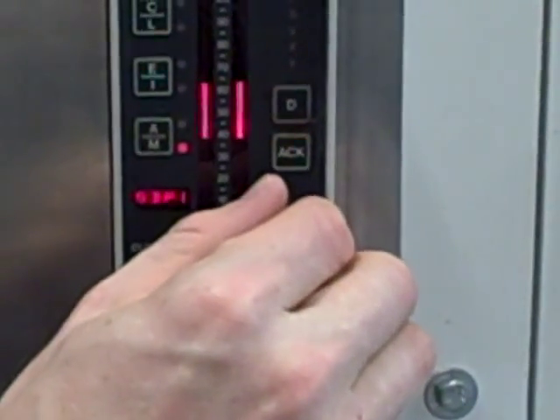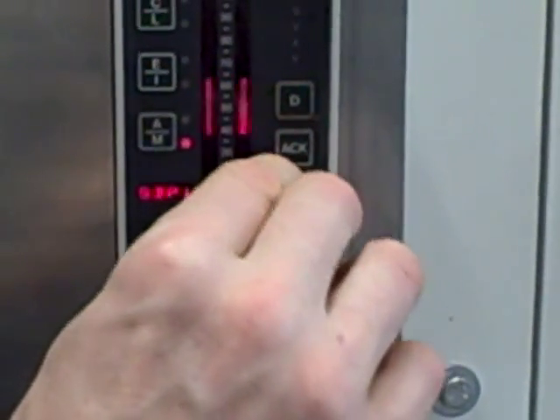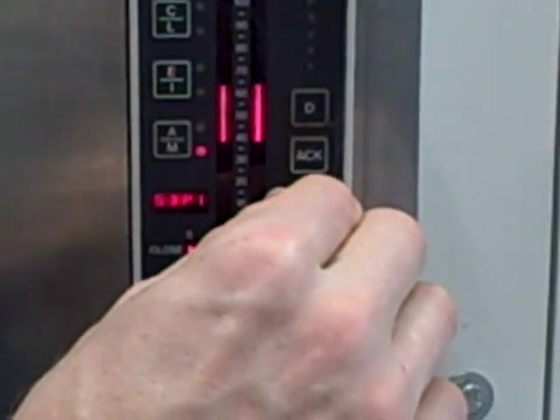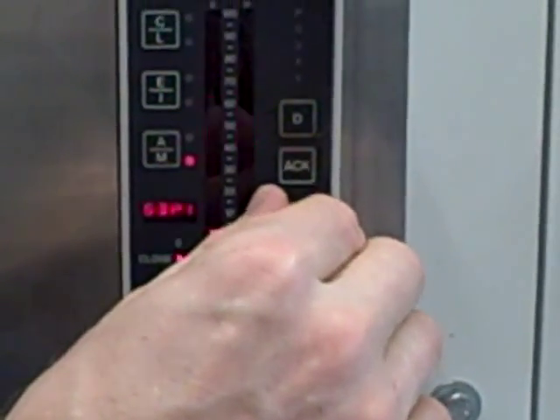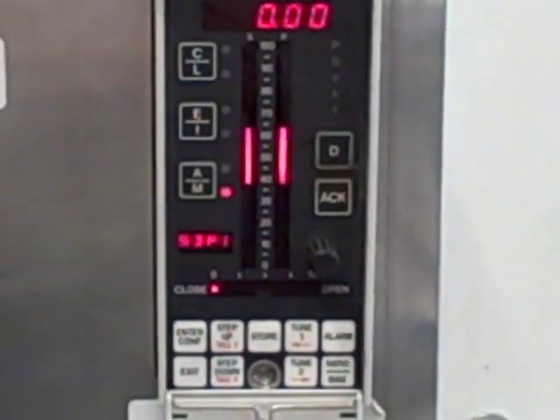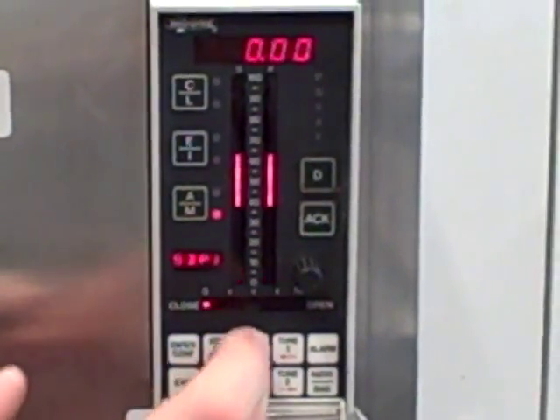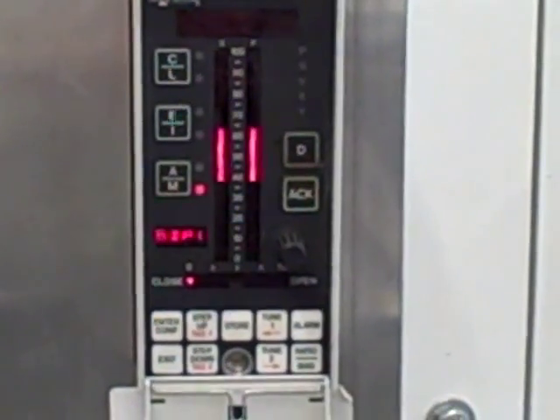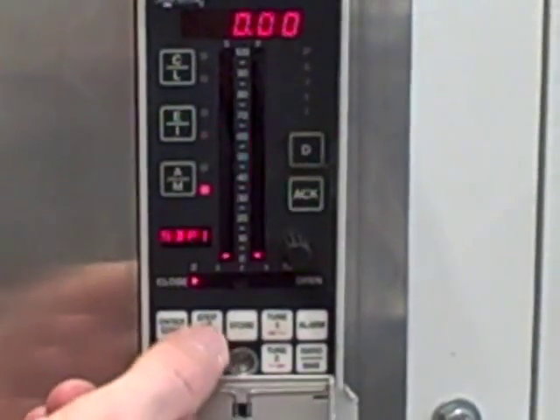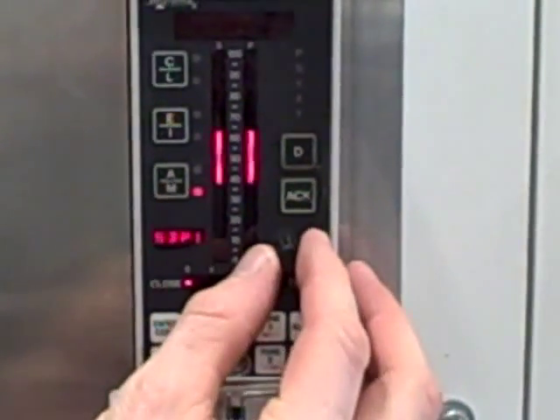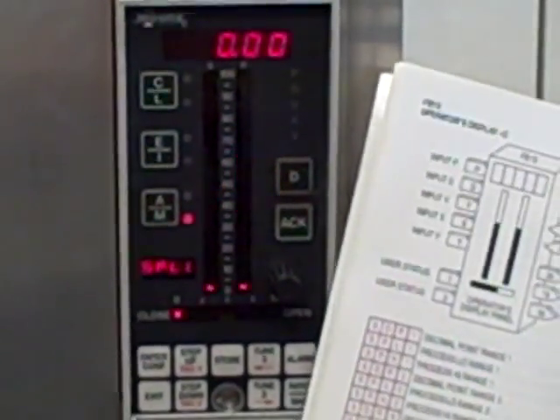That's how I set the number of decimal points I have there. So I shouldn't say number of decimal points, the number of digits past the decimal point. I'm happy with what I have, so I hit store. I will now step up into the menu structure and move one over to my next parameter, SPL1. SPL1 is process low range value 1. Stepping down into that, it shows 0.